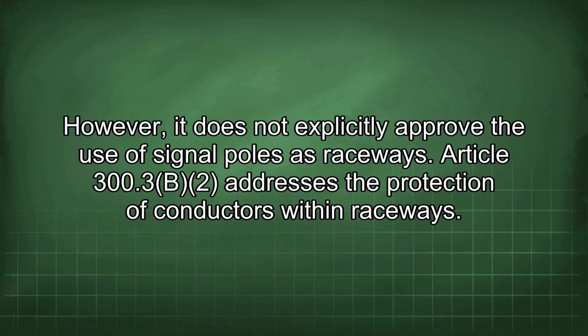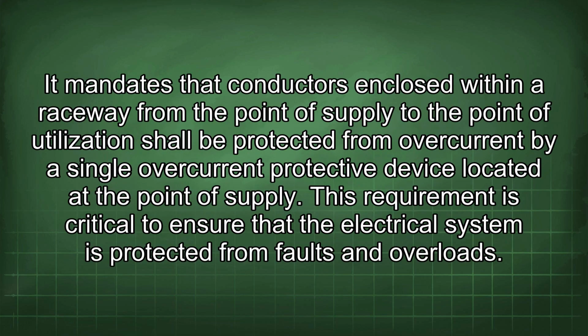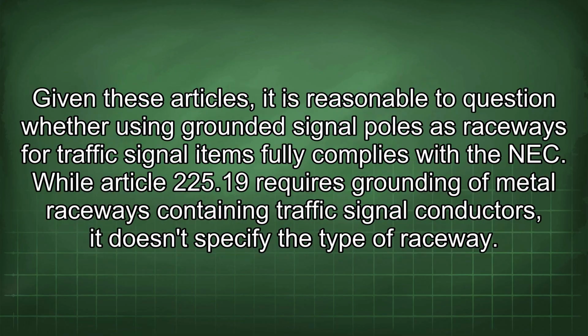Article 300.3b2 addresses the protection of conductors within raceways. It mandates that conductors enclosed within a raceway from the point of supply to the point of utilization shall be protected from overcurrent by a single overcurrent protective device located at the point of supply. This requirement is critical to ensure that the electrical system is protected from faults and overloads. Given these articles, it is reasonable to question whether using grounded signal poles as raceways for traffic signal items fully complies with the NEC.